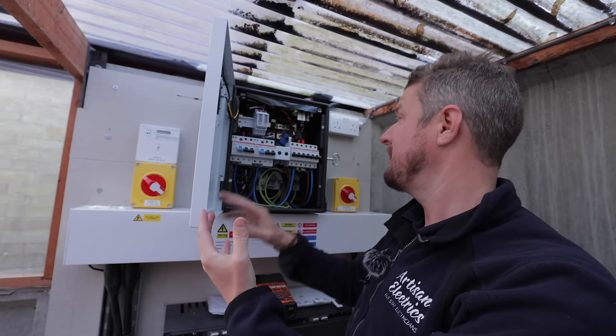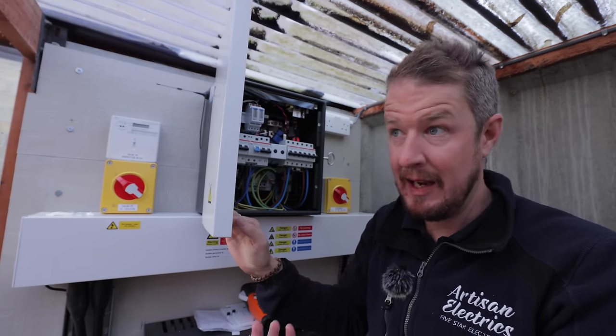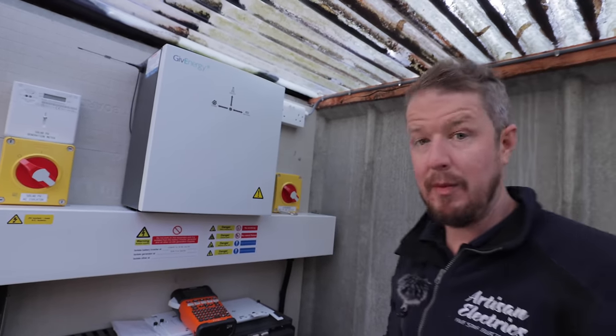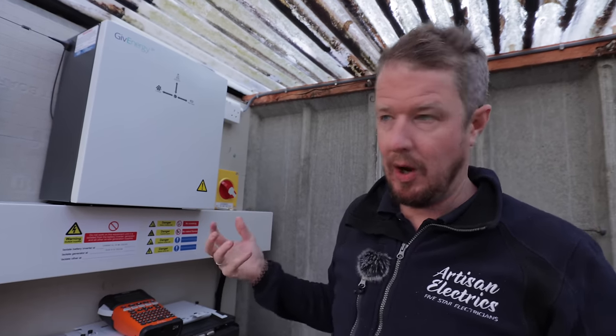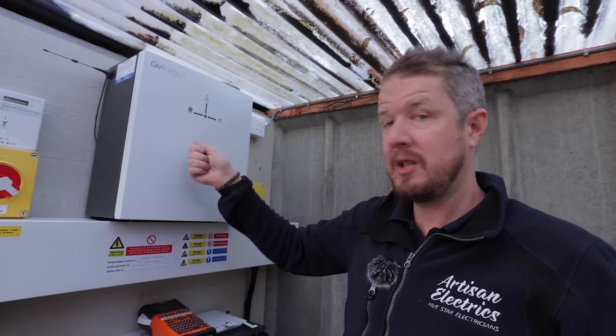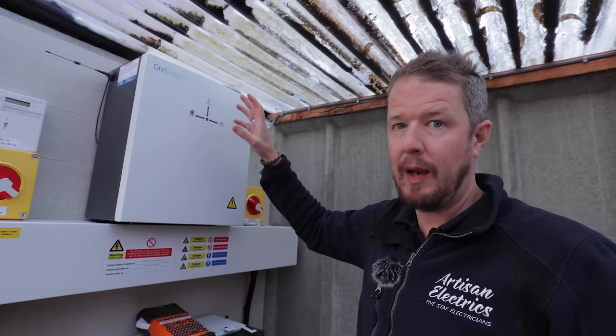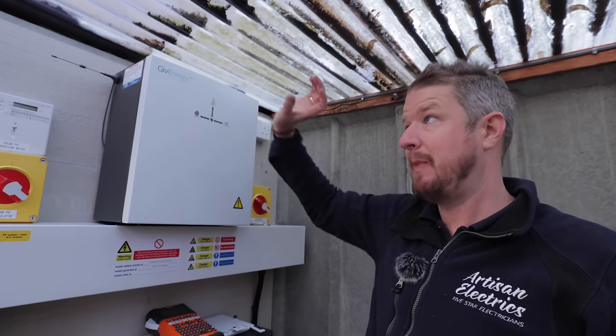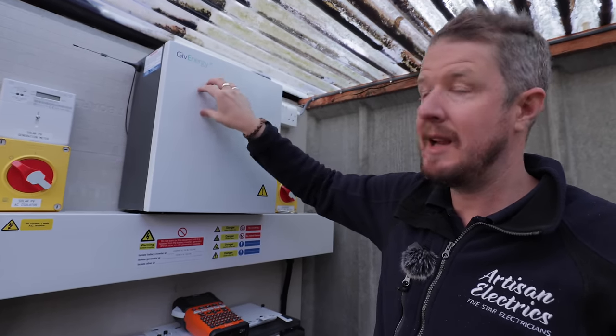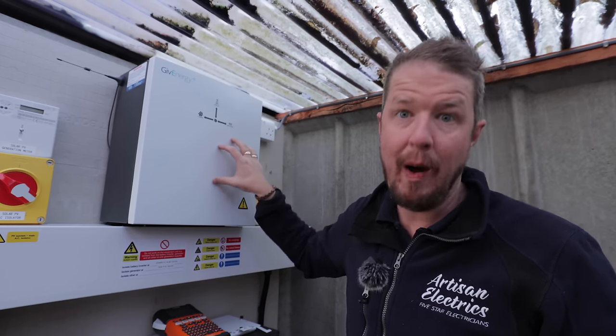When the grid connection resumes, the system detects it and automatically changes back, connecting us to the grid almost instantaneously — to the point where you won't even see a light bulb flicker. In terms of communications, the GivEnergy gateway communicates with the battery via a Cat6 data cable with RJ45 plugs on each end, telling it when to charge and discharge. That runs through the flexible conduit along with the power cables. The inverter in the loft is essentially a dumb inverter — all the gateway needs is a CT in here to read how much solar is being produced, so all solar generation data comes through the gateway rather than from the inverter.